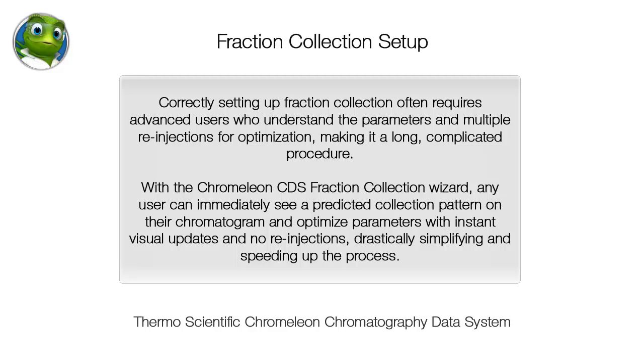Correctly setting up fraction collection often requires advanced users who understand the parameters and multiple re-injections for optimization, making it a long, complicated procedure. With the Chromeleon CDS Fraction Collection Wizard, any user can immediately see a predicted collection pattern on their chromatogram and optimize parameters with instant visual updates and no re-injections, drastically simplifying and speeding up the process.